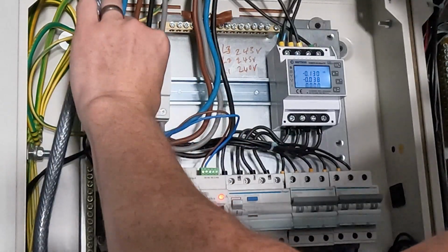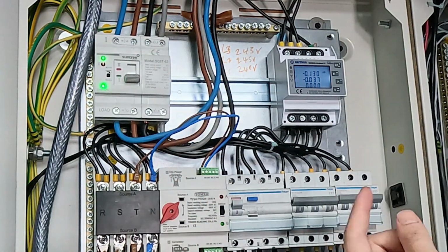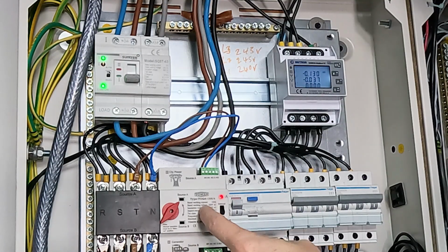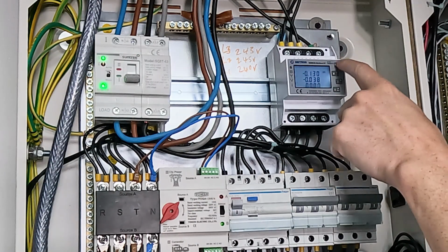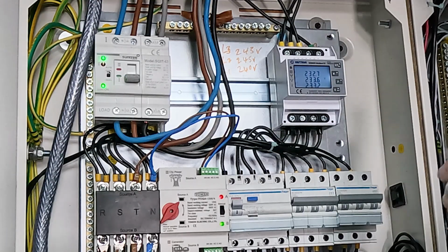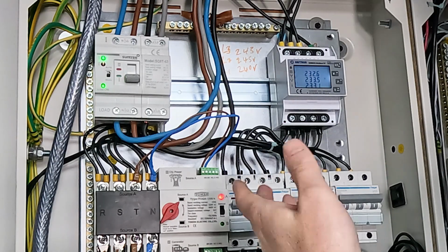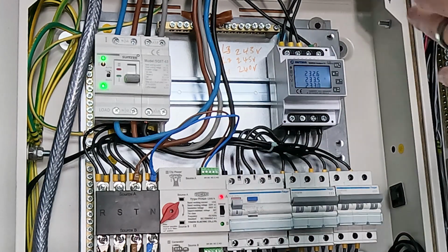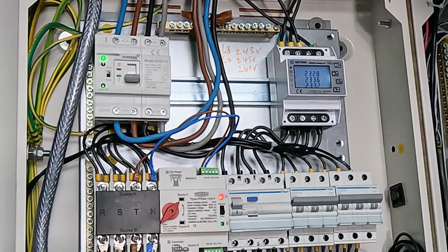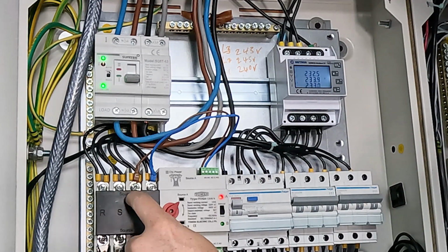Just turning the grid back on, the inverter will synchronize. This position is still connected to the backup, so the output voltages here will actually be your 230s, which is the output of the inverter. My grid voltages are more the 240s. And that's how I know it's connected to the backup. Then my inverter will take about 60 seconds to connect back up and synchronize to the grid voltages, and then it'll whack it in, and source A will effectively be the grid voltages, because the inverter will be letting the grid voltages through it and into source A.